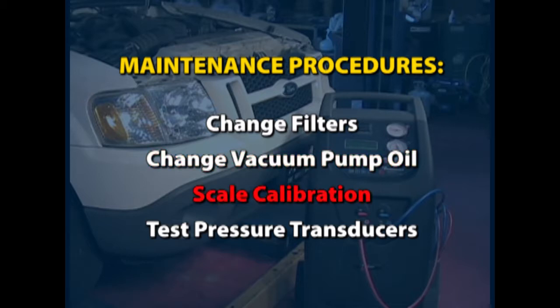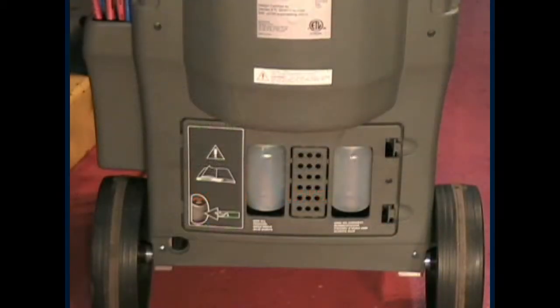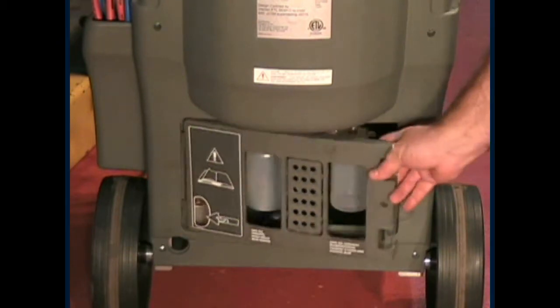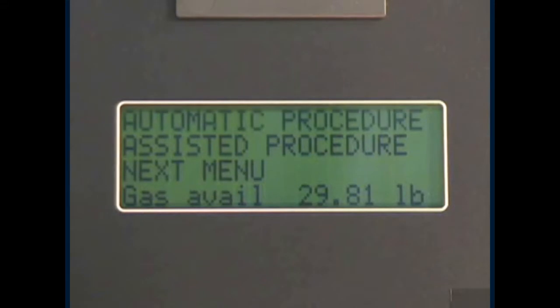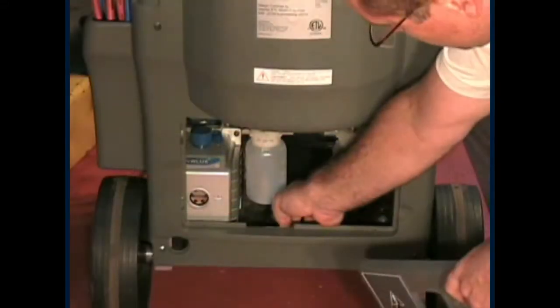The scale calibration can be tested by locating the 1-pound weight provided with the unit. It is either behind the right panel cover or behind the lower back panel cover. First, observe the gas available on the display, then hang the weight on the tether attached to the tank.